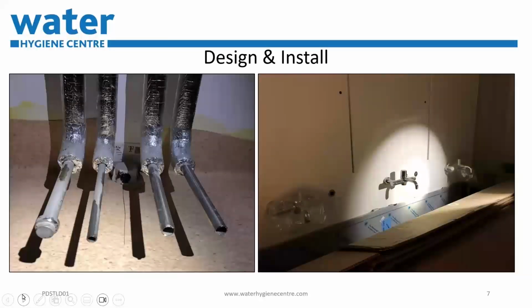So we see lots of organisations that have refurbishments or installs looking like this, where on the left-hand side photograph, anybody can spot where the error is, but it's not a capped off supply. So there's obviously an opportunity for detritus, airborne particulates, contamination to occur there. And on the right-hand side of the photograph, the middle outlet is not being bagged. So it's again open to the environment and open to other sorts of contamination.